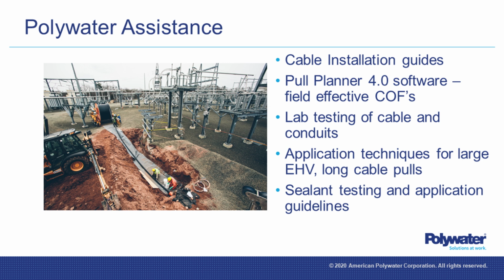There was a group that did a study on coefficients of friction—that's the rub between the outside of the cable jacket and the conduit surface. So if you have a PVC jacketed cable on PVC conduit, that's one measurement of coefficient of friction. If it's a PVC jacketed cable on rigid steel conduit, that's a different coefficient of friction, and so on.